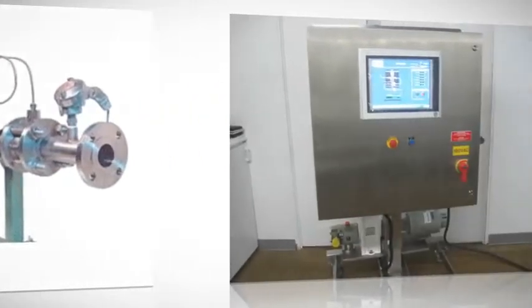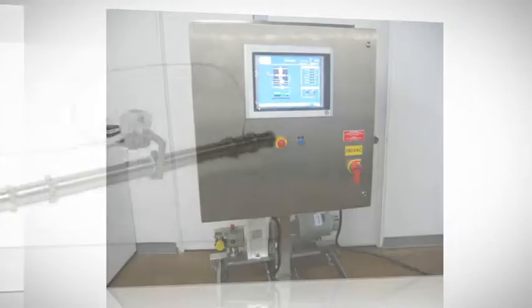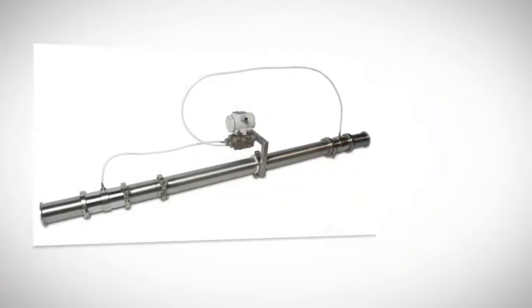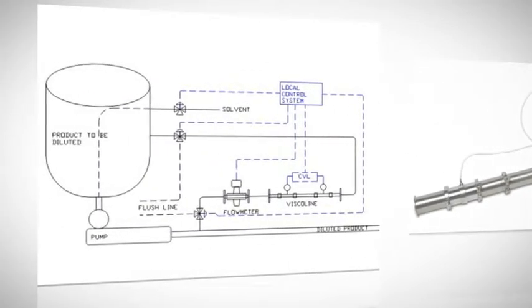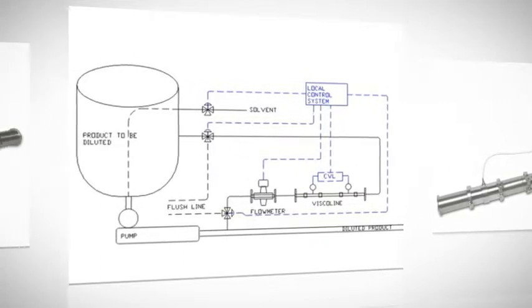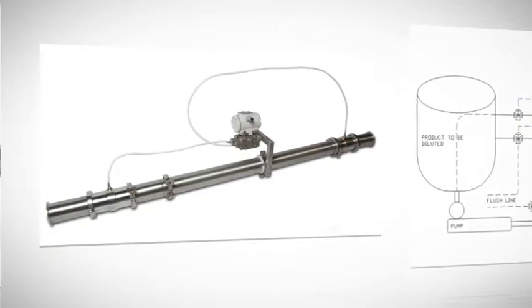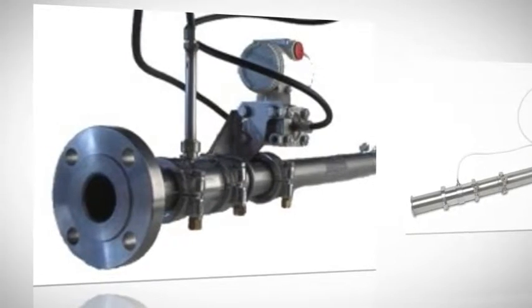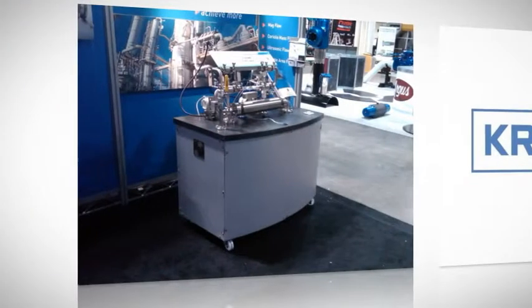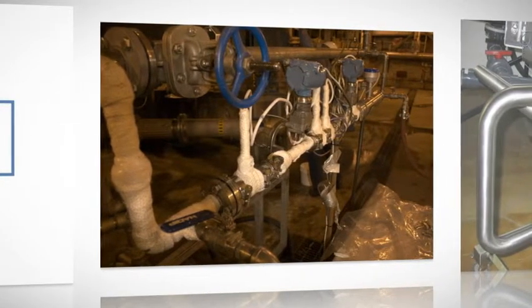What are some of Viscoline's key features? It features all-stainless steel construction with no moving parts. There's no need for on-site calibration. It's available with integrated flow measurement for continuous process applications. It meets regulatory policy on metrological traceability. It provides continuous viscosity measurements with analog or digital process outputs such as pulse or Modbus protocol. And, perhaps most importantly, it's extremely reliable, featuring a repeatability of 0.2% and a resolution to a tenth of a centipoise.